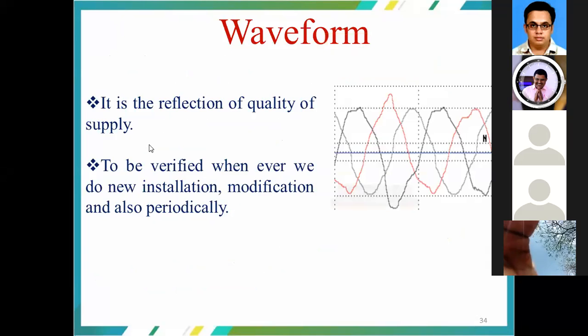And when it comes to the major problem, that is the distortion of the waveforms, the waveform is a reflection of the quality of the supply. If we are going to have a pure sinusoidal waveform, then the waveform shape is going to follow the sinusoidal pattern. And the waveform is to be verified whenever we do new installations of converters or any renewable energy sources, and we need to have the modifications, and also we need to have periodical verifications. In this way we are able to ensure the proper quality of the waveform, and if the quality of the waveform is better, we are going to have reduced power quality issues.